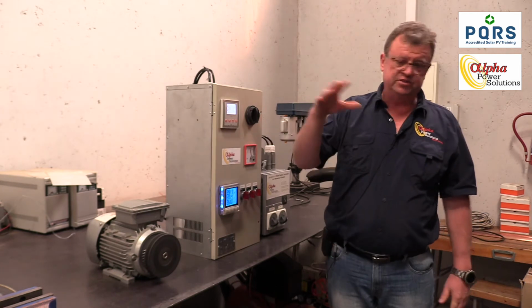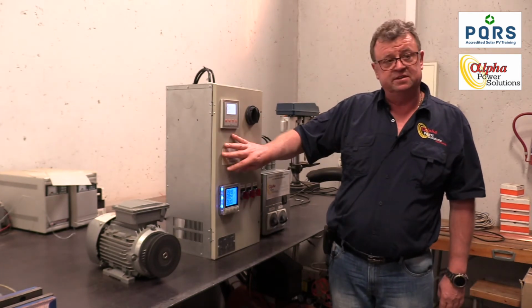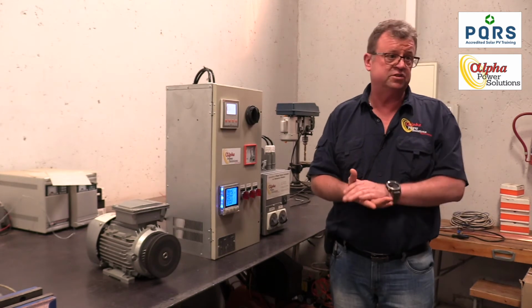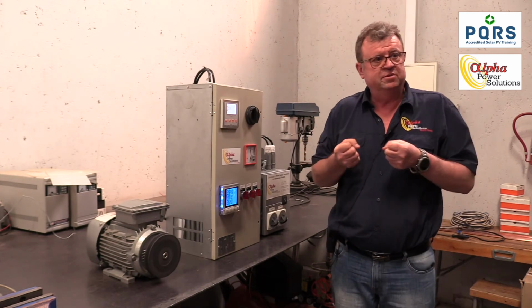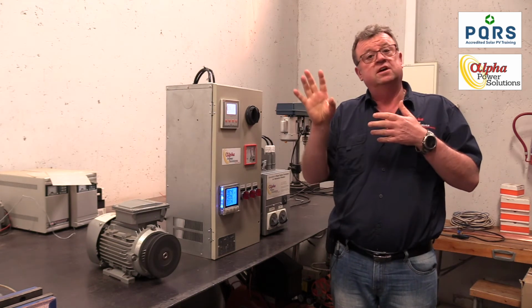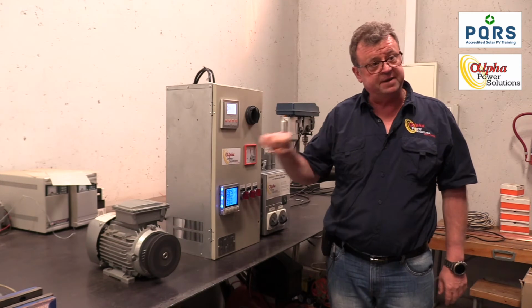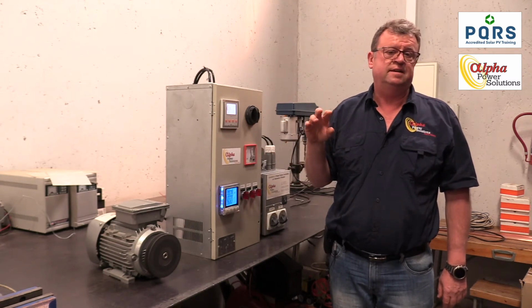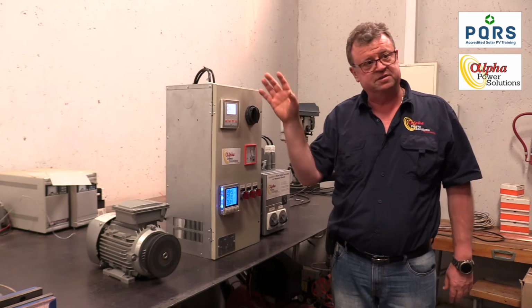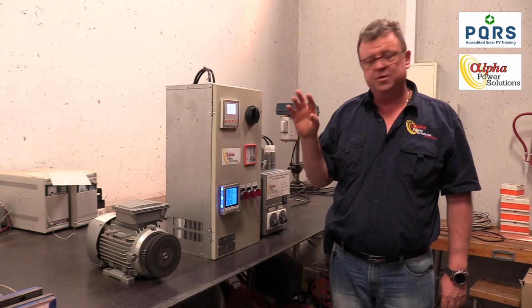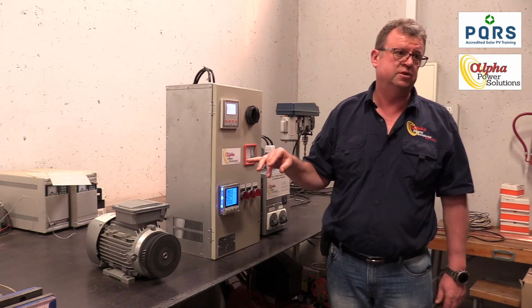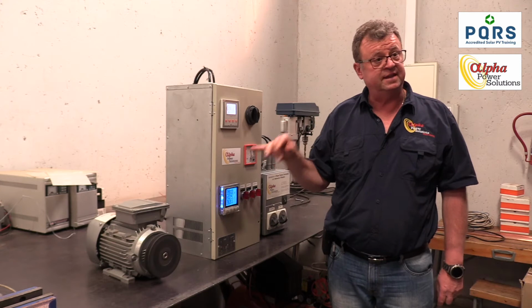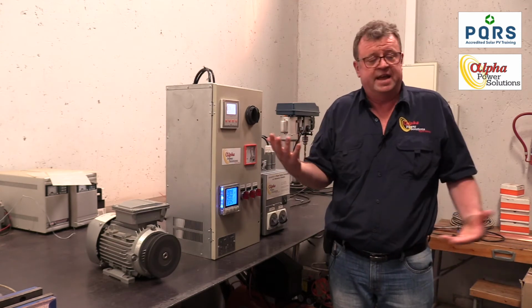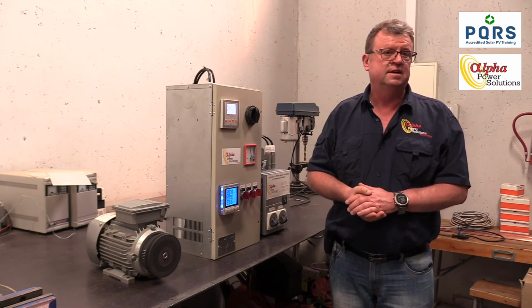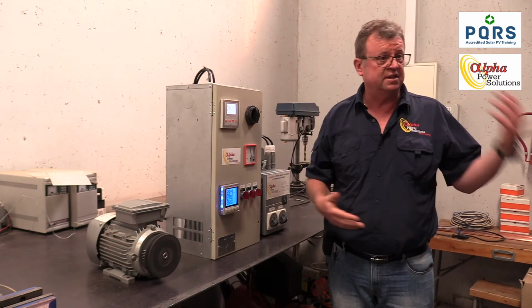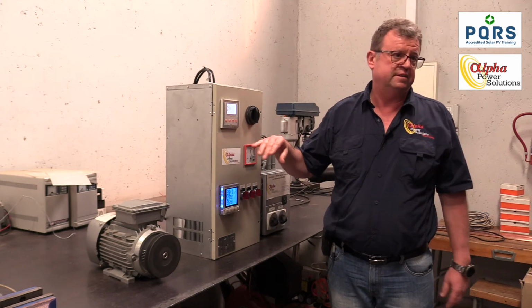The other thing, and I'll mention it in the presentation as well, is that capacitors represent a low impedance path for voltage surges. So what happens is almost like a vacuum cleaner. It attracts the voltage surge away from the rest of the equipment, but that means that the panel takes most of the knock. As a result, you save the plant a bit, but you blow up your capacitors. So we always recommend that our customers put in class 1, class 2 surge protection. Voltage surges are going to happen more and more as the infrastructure deteriorates, where surge protection on the overhead lines and all that is no longer working, so it's very important that you protect the equipment.